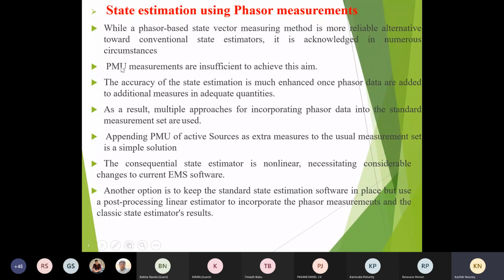So this is state estimation using phasor measurement units. In the method you are using, PMU measurements are insufficient. Only PMU cannot do everything. So PMU data has to be combined with state estimation data. That's why we are saying here that the accuracy of state estimation is much enhanced when phasor data are added to additional measurements in adequate quantities. As a result, there are multiple approaches. Several approaches are there for incorporating phasor data into the standard measurement set.